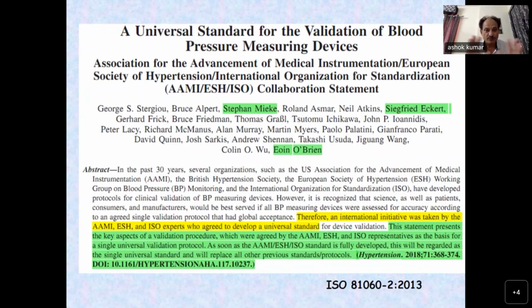This is the gist of this ISO. What is the gist of ISO? The device which is developed or required for type approval or for testing should have a plus or minus 5 mmHg error with respect to a standard device, and the standard deviation of the error should not be larger than plus or minus 8 mmHg.